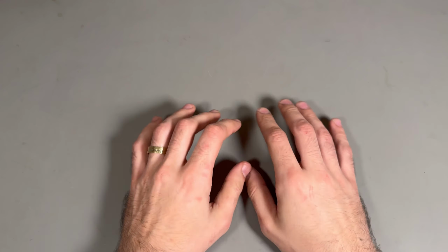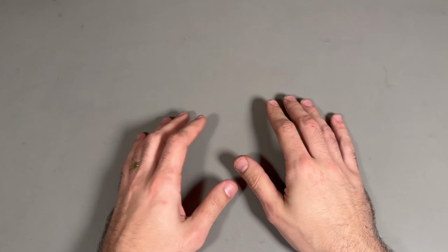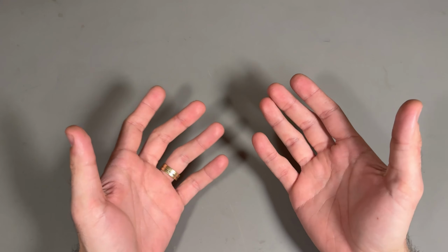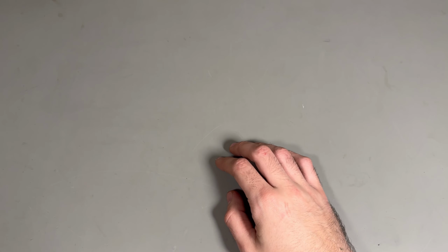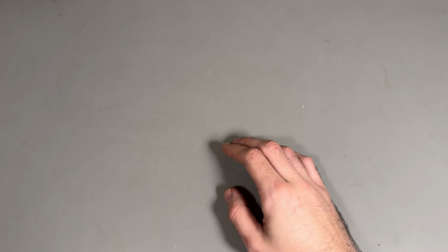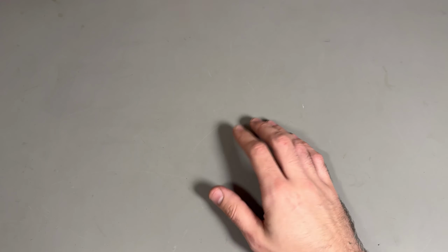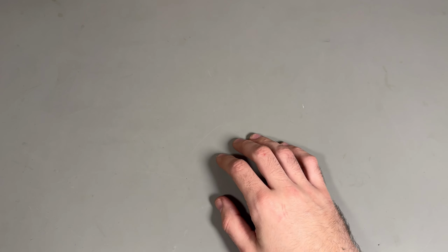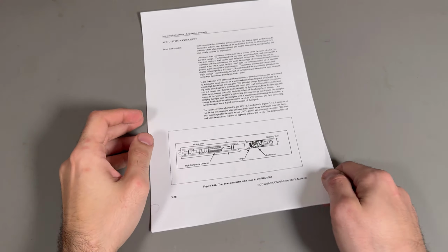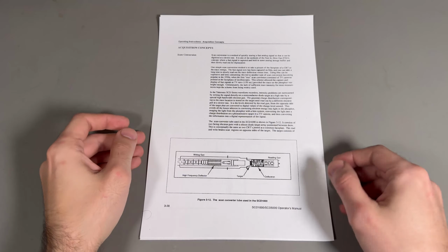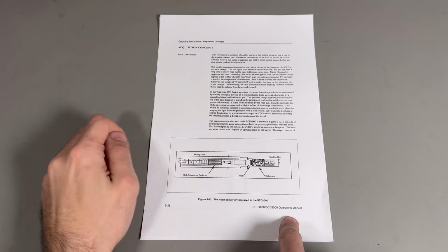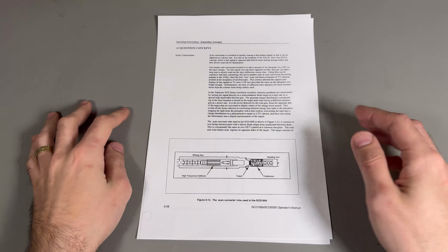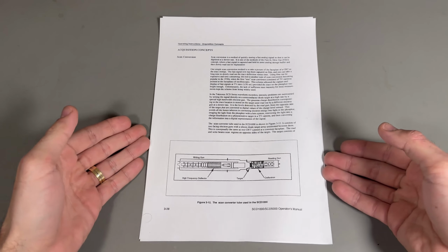Your second option was the 7104, as I said, which had a gigahertz of bandwidth, but that might not have been fast enough. So what Tektronix came up with, I think, was the scan converter tube. And here's an excerpt out of the device's operator manual, and we have a little look at what's inside the heart of the instrument.